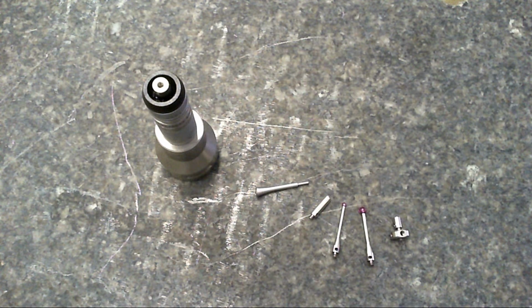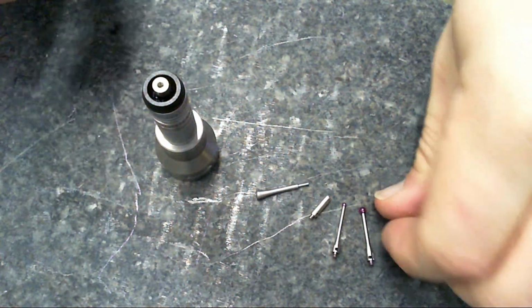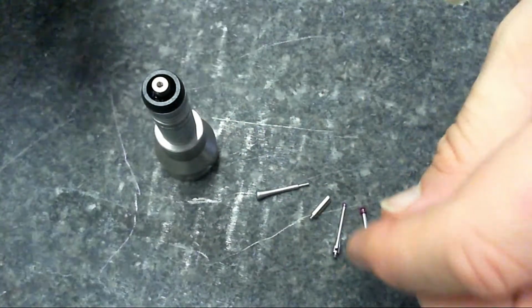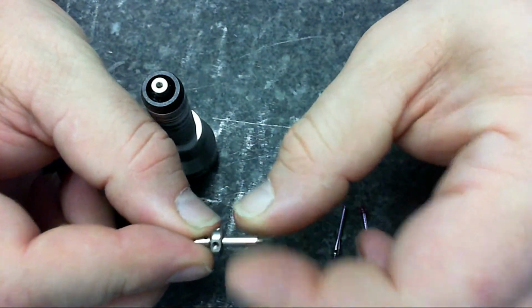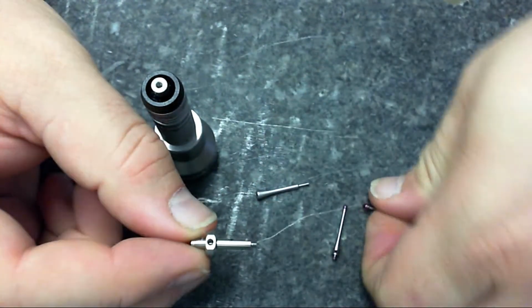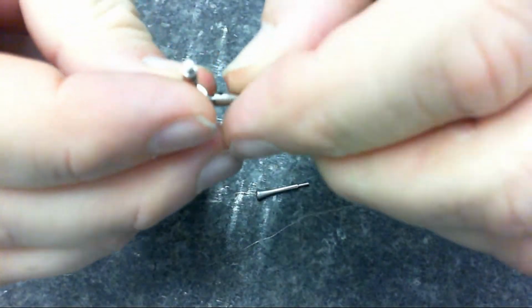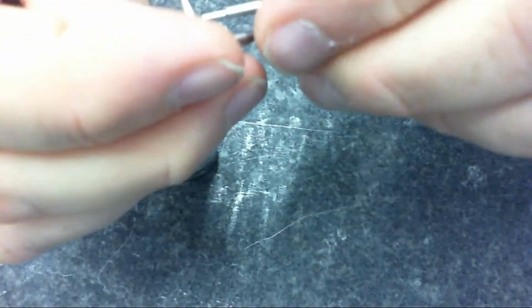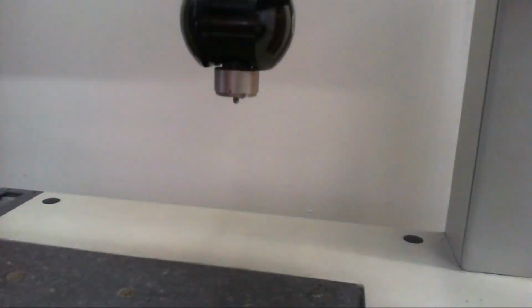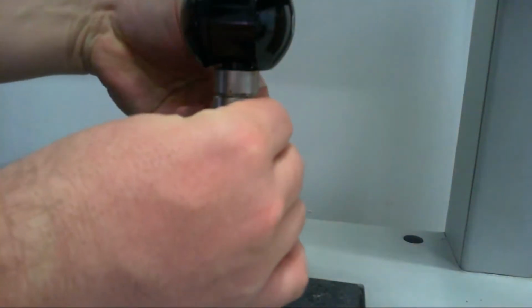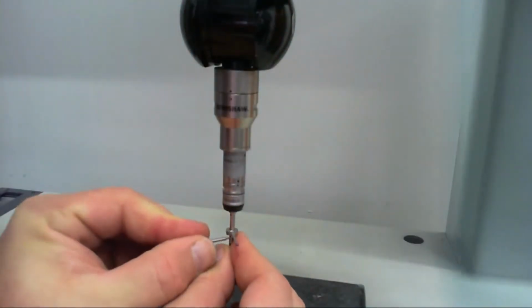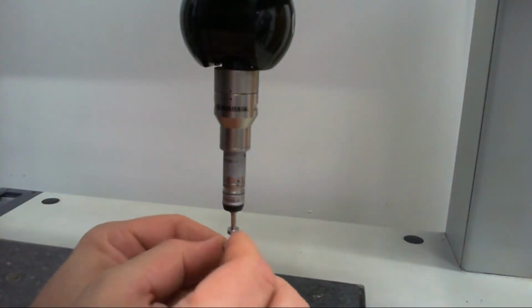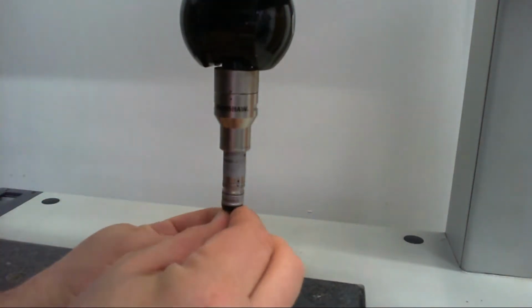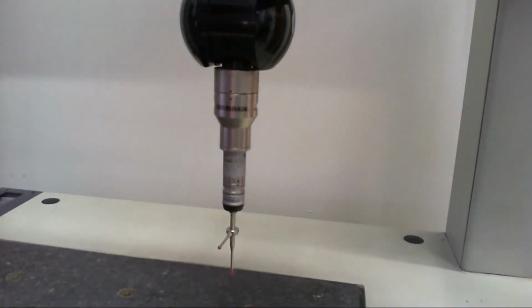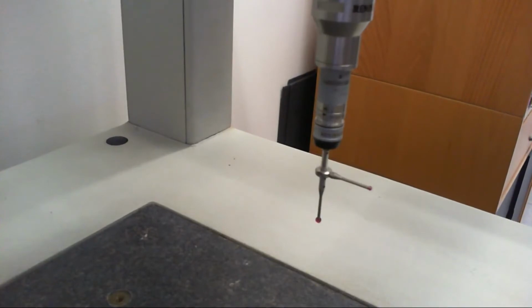The first step is to build a suitable probe configuration. Due to the span of the PH10 head, the T configuration is preferred in order to reduce the CMM error. Now we are mounting the probe in the PH10 head, and then we make sure to have the stylus properly aligned, in order to avoid the so-called shanking during the inspection. A shanking is a false measure that we get when the part is touched by the shaft of the stylus and not by the ruby ball. This is normally due to a misalignment.